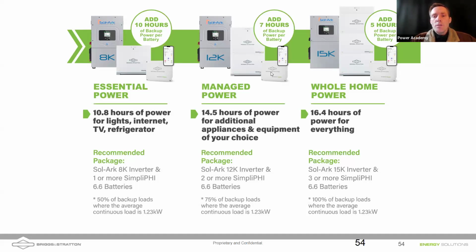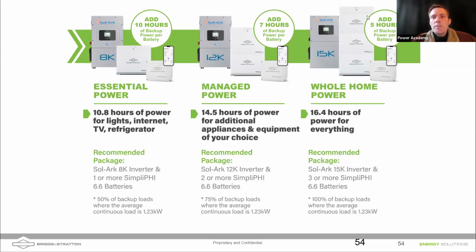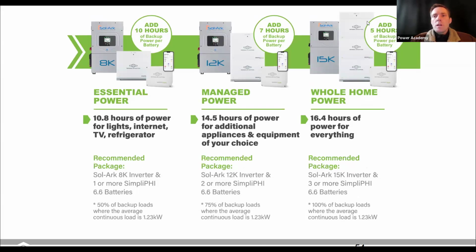Up to 80 amps can be dropped off based on battery percentage. That's whole home backup with the Sol-Ark 15K. We're showing just a single stack of batteries there, but many customers are choosing to install multiple 20 kilowatt-hour stacks. And for each individual module that you add, you get a little over 5 hours of backup time. So it's quite an easy system to install as well.